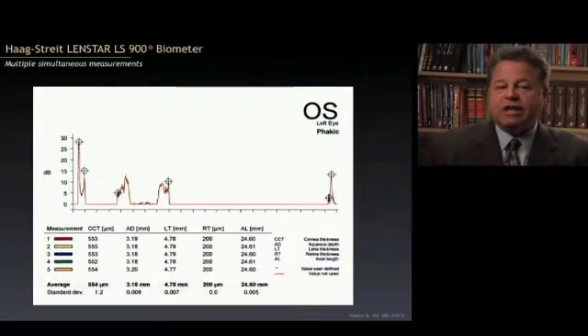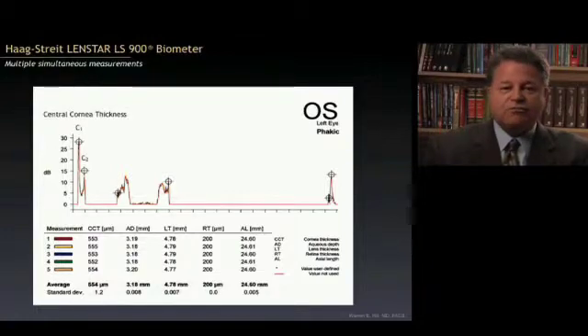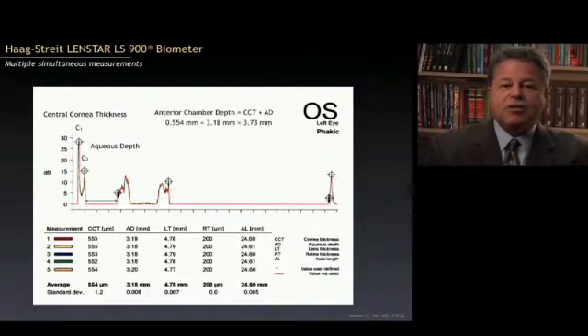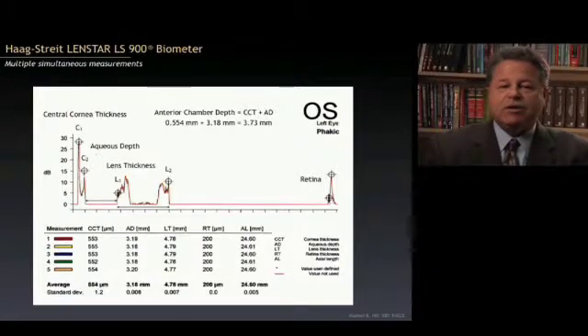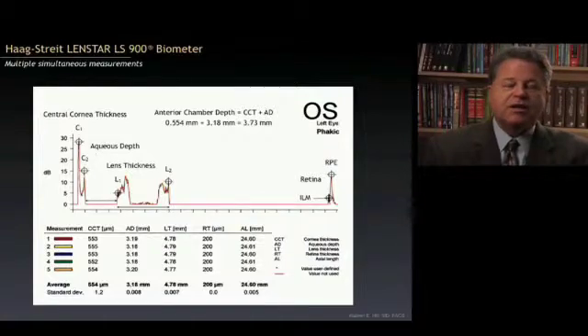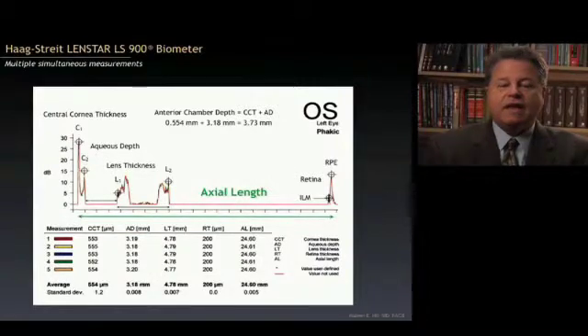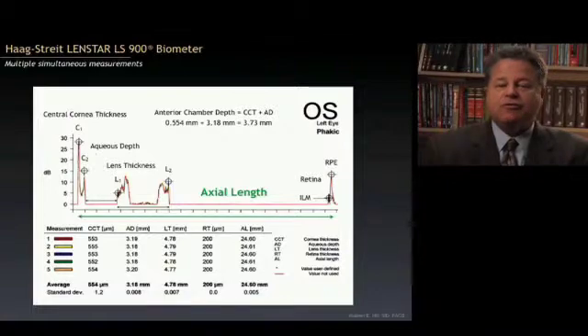This is what the axial length display looks like for the LenStar. We have the anterior and posterior corneal spikes, the aqueous depth, and if we add central corneal thickness together with aqueous depth we get anterior chamber depth. Lens thickness shows the anterior and posterior lens capsule and anatomy in between. Then we have the vitreous cavity and two spikes on the retina — one is the vitreoretinal interface or internal limiting membrane, and the other is the pigment epithelium. Put it all together and that gives us the axial length. We have five measurements, and information from all five gives us a final value with a standard deviation.